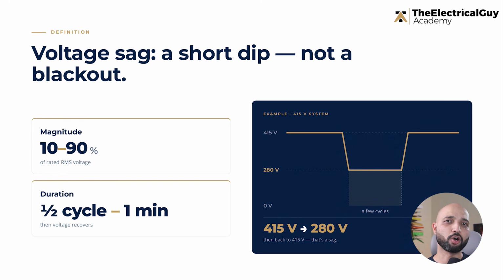A voltage sag is a short duration reduction in RMS voltage below the normal operating level, typically between 10% to 90% of the rated voltage, for durations from 0.5 cycles to 1 minute. In simple words, voltage sag means the voltage has dropped for a short time, but it has not become zero. For example, suppose your system voltage is 415 volts. During a disturbance, the voltage suddenly drops to 280 volts or 250 volts for a few cycles and then comes back to normal. That event is called a voltage sag.